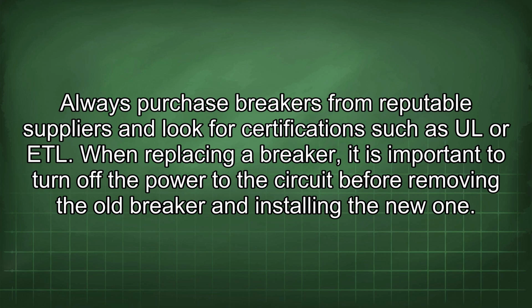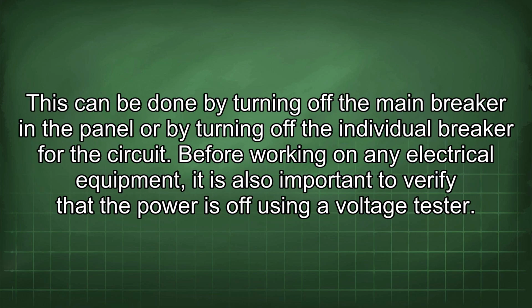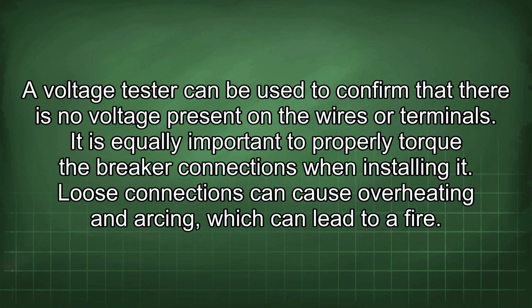When replacing a breaker, it is important to turn off the power to the circuit before removing the old breaker and installing the new one. This can be done by turning off the main breaker in the panel or by turning off the individual breaker for the circuit. Before working on any electrical equipment, it is also important to verify that the power is off using a voltage tester. A voltage tester can be used to confirm that there is no voltage present in the wires or terminals.